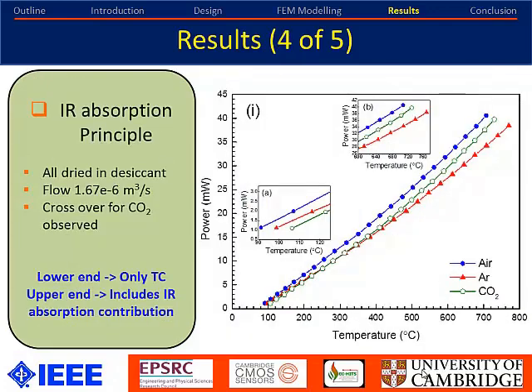For infrared absorption mode: the sensor emits infrared radiation from 0.8 to roughly 12 microns — it's a wide-band infrared emitter. We have three curves here for dry synthetic air, argon, and CO2, all passed through a desiccant. At low temperatures, air sits at the top, argon in the middle, and CO2 at the bottom because CO2 has lower thermal conductivity. However, as temperature increases toward around 700°C, the curves flip — CO2 now sits between argon and air — because CO2 absorbs infrared radiation at approximately 4.26 micron wavelength.